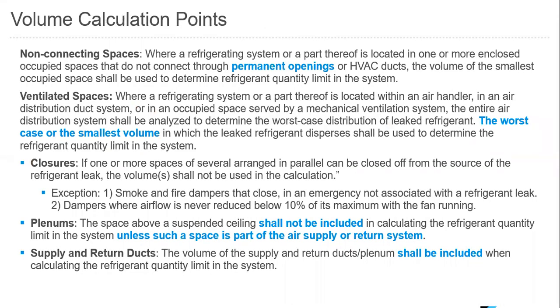So there are 2 different types of spaces. We have non-connecting spaces. That's where we have spaces that are very isolated. They don't have any permanent openings. We also have ventilated spaces where we're going to have the ability to ventilate that space. And within ventilated spaces, we actually have 3 different ways that we ventilate spaces. It can be through a closure, which could be a damper or an undercut and a door. We also have plenums, although we can't really include the plenum in that space volume within that ventilated space. And then we have supply ducts and returns. And the volume of those ducts and returns have to be included when we calculate the refrigerant quantity within that ventilated space.